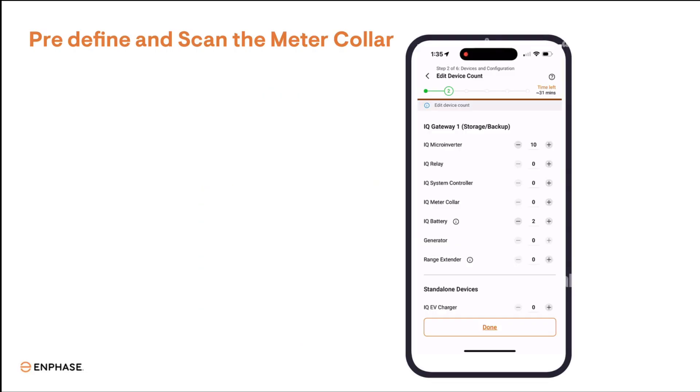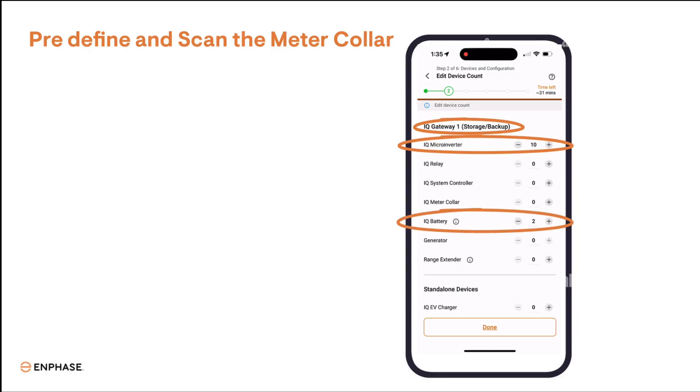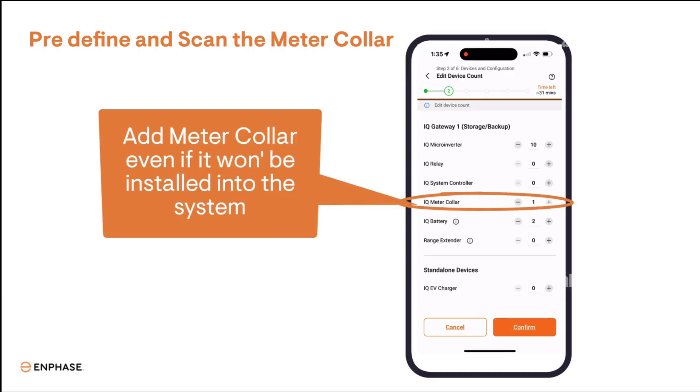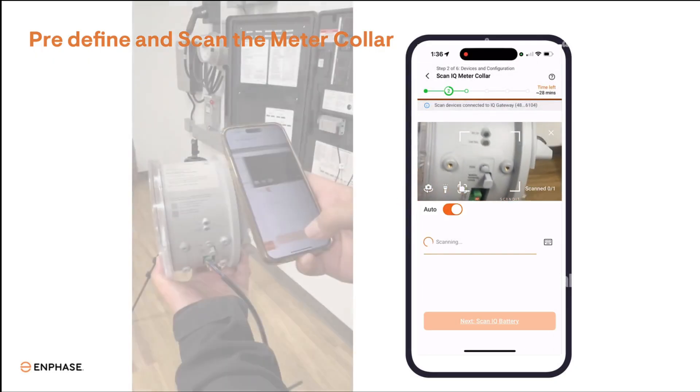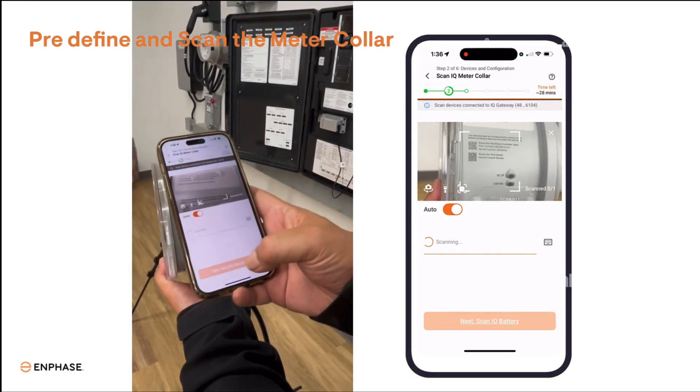In the Installer app, Step 2 — Devices and Configuration — define the IQ Combiner Count, Micro Inverter Count, and Battery Count as normal, and add one meter collar to the count, even if it will not be installed by the utility yet. Scan all of the device serial numbers, including the meter collar serial number QR code, even if the meter collar won't be installed on that day.